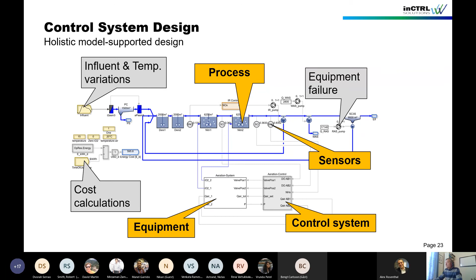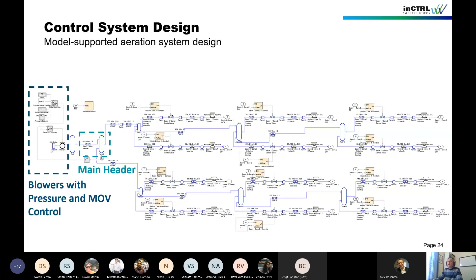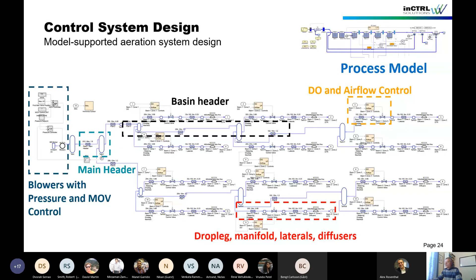That means you have to have a very detailed model of your aeration system. In this case, it's with blowers, with pressure and MOV control, main header, basin header, and then the drop legs, manifold, laterals, diffusers, and then you have DO and airflow control. And of course, it's also connected with the process model to calculate or estimate the oxygen demand of the process.